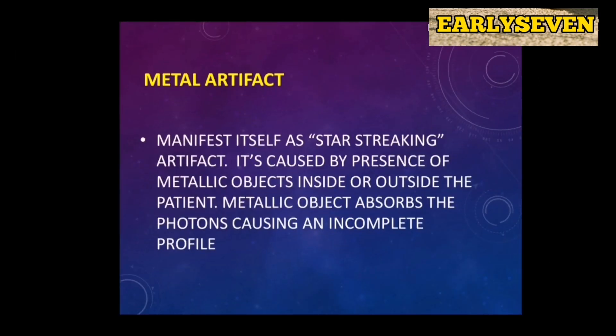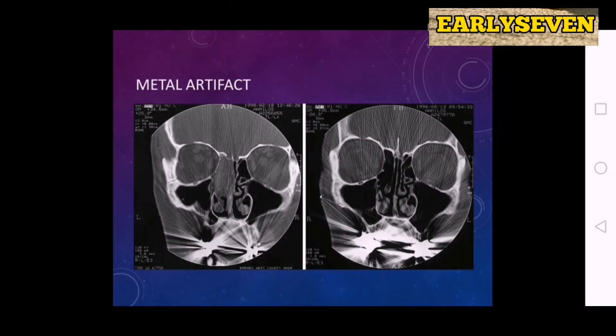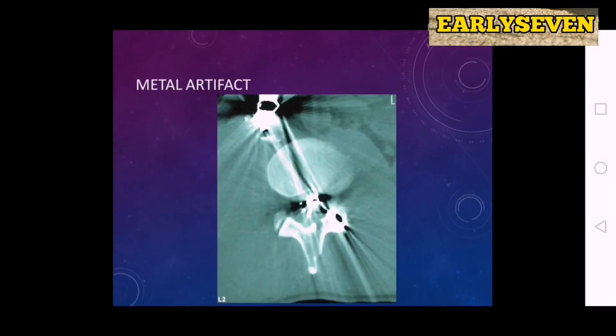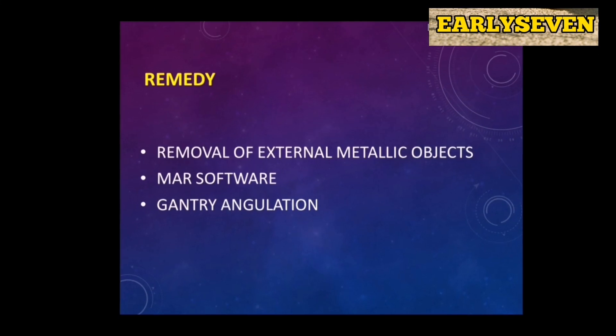Another type of artifact is the metal artifact. It manifests itself as a star-streaking artifact caused by the presence of metallic objects inside or outside the patient. The metallic object absorbs the photon, causing an incomplete profile. The remedy for metallic artifact is the removal of external metallic objects, the use of MARS software (metallic artifact removal software), and gantry angulation.